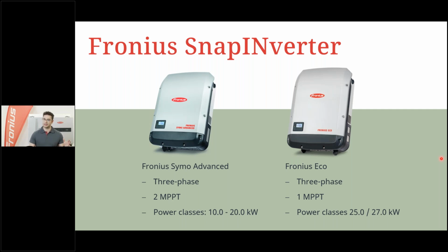It's the Fronius Symo Advanced and the Fronius Eco. You might know there's an additional word in the naming, the Advanced. It has all the features of the Fronius Symo, but one more: an additional arc guard, meaning a DC arc can be detected and the whole system can shut down. It's a safety feature included in this product. The Fronius Symo Advanced comes as a 3-phase inverter with 2 MPP trackers and 10 to 20 kilowatt power classes. So it's the flexible one, you could say.